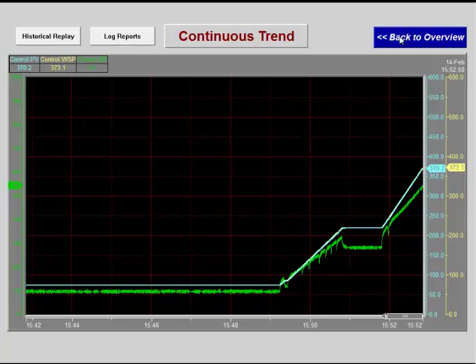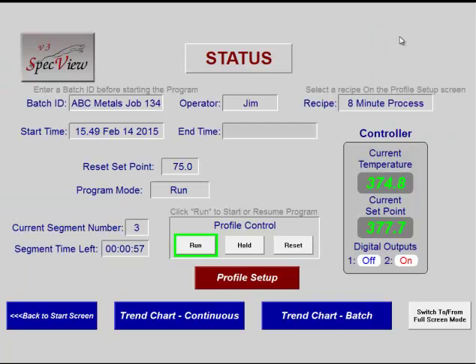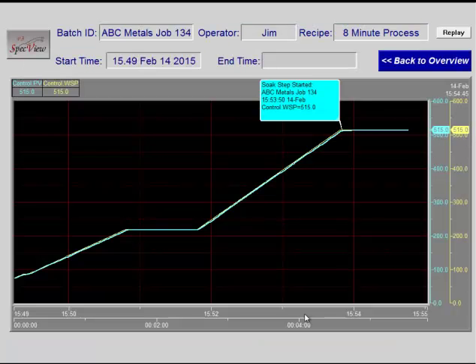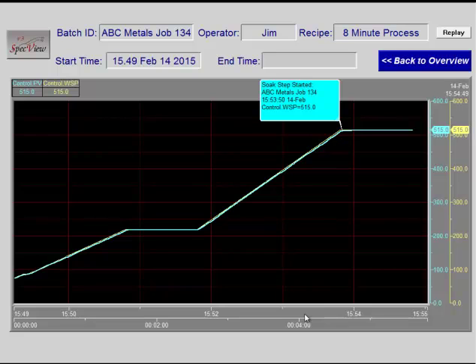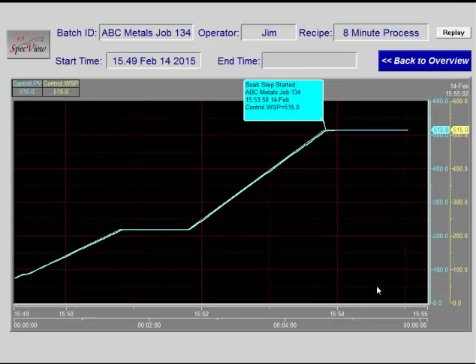Click Back to Overview. The Trend Chart Batch button selects the new, non-scroll chart. When the batch was started, the chart was automatically cleared. The chart started on the left and when the trace reaches the right-hand end, the chart time base is increased. In this way, the whole process will always be on the chart, whether it lasts 10 minutes, 10 hours or 10 days.